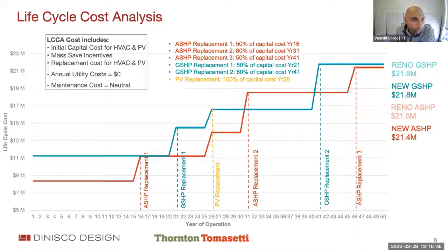I would also—Simon is online too, right? I'll have Simon chime in here. Based on our internal discussion within the design team, we talked about 50% of capital cost replacement for the air source heat pump at year 16, and at year 31 we expect 80% of the cost of replacement. This repeats after that, around year 46 for the air source heat pump, or 41, sorry. For the geothermal system, we anticipate a similar kind of schedule but a bit more stretched out, one around year 21 and one at year 41.